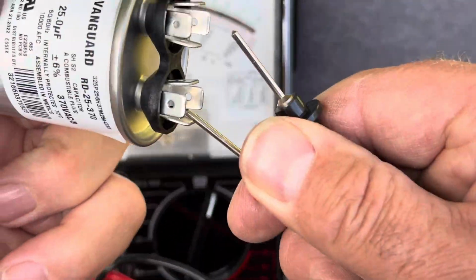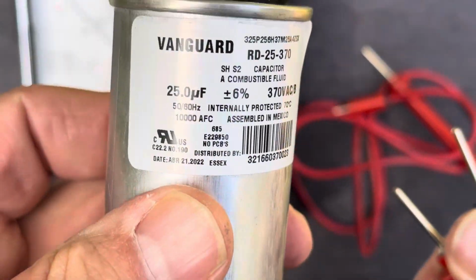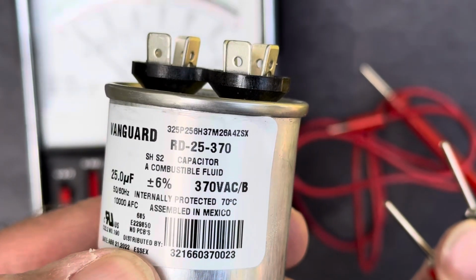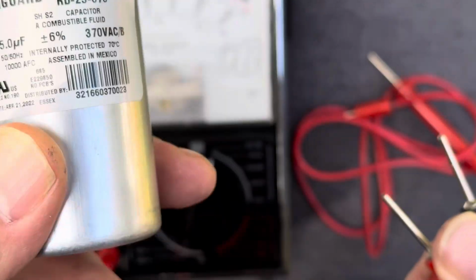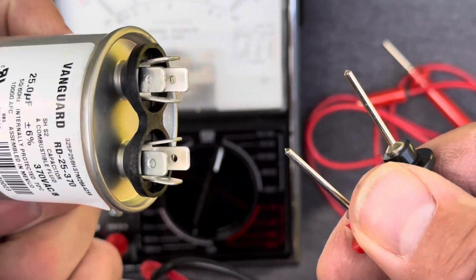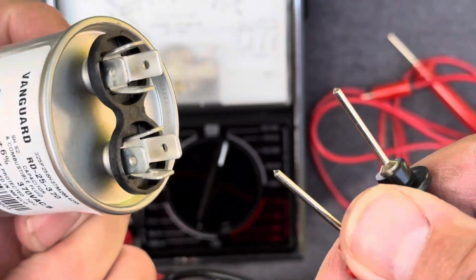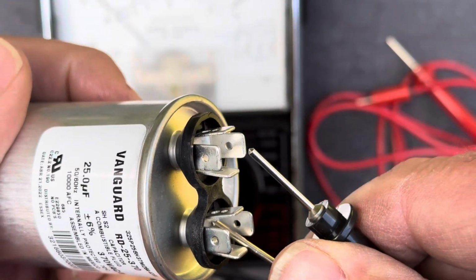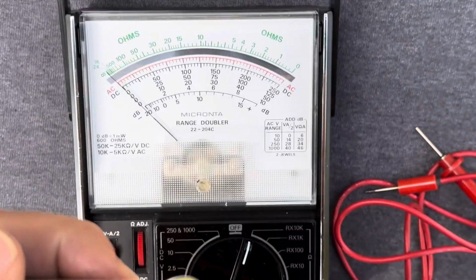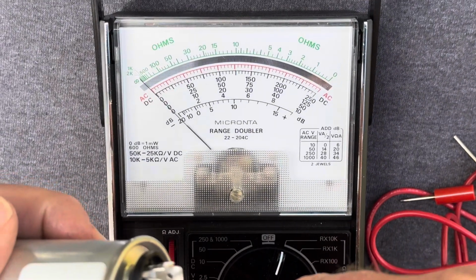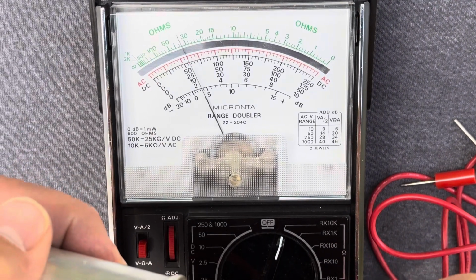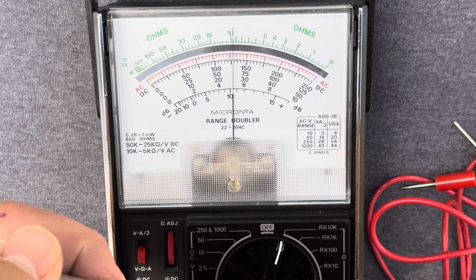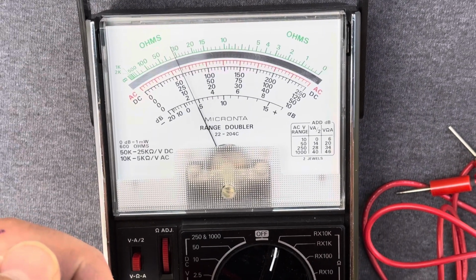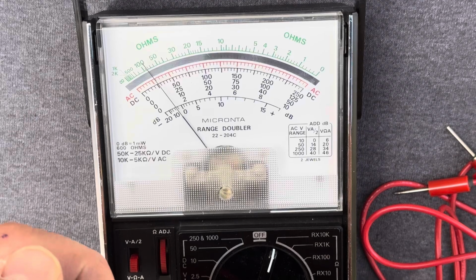Now we take the new one and do the same thing. By the way, that one is also 25 microfarad, 370 volts AC - same rating, same capacitor, same size. If you watch the meter on this one when I touch it to the terminals, it does deflect and fall back towards infinity. So that shows this is a good capacitor.